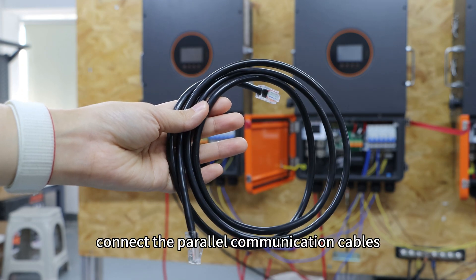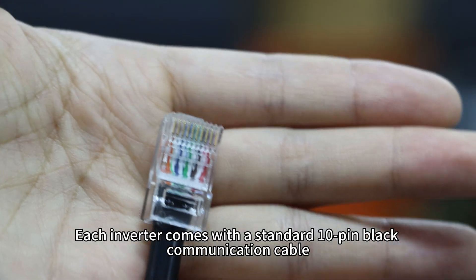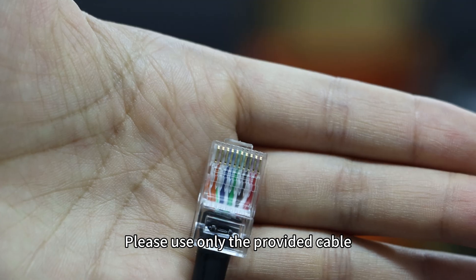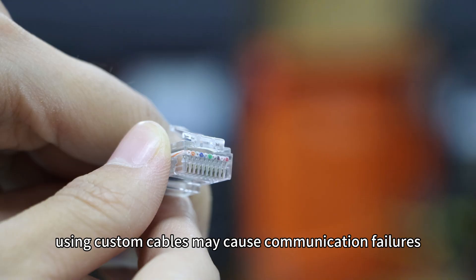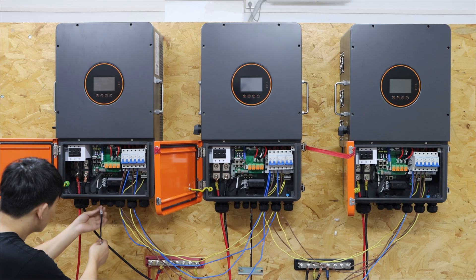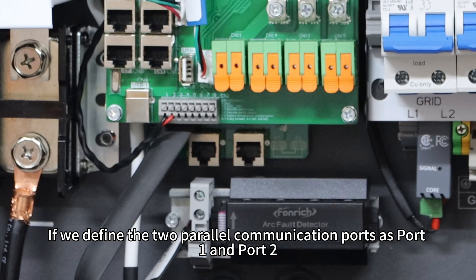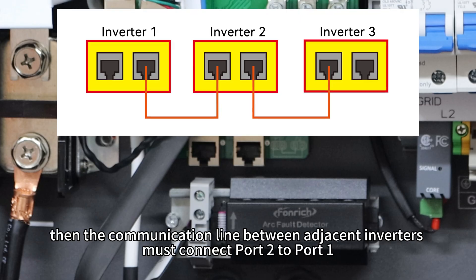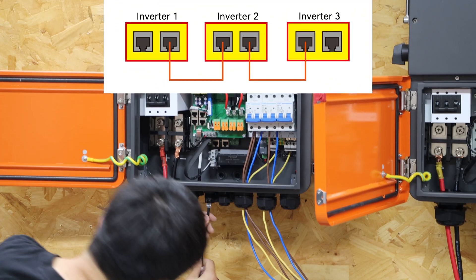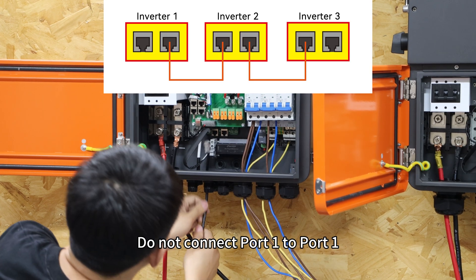Next, connect the parallel communication cables. Each inverter comes with a standard 10-pin black communication cable. Please use only the provided cable — using custom cables may cause communication failures. If we define the two parallel communication ports as port 1 and port 2, the communication line between adjacent inverters must connect port 2 to port 1. Do not connect port 1 to port 1.